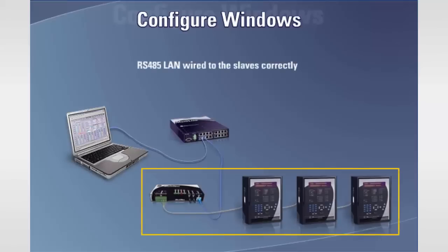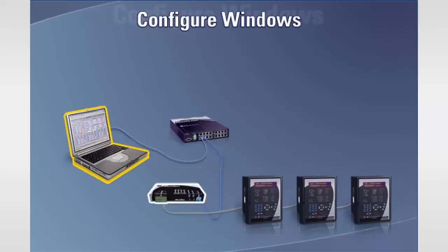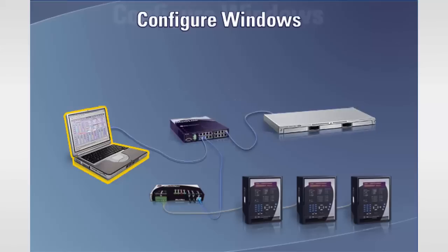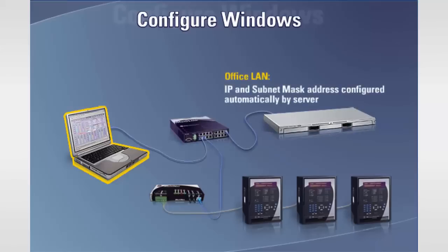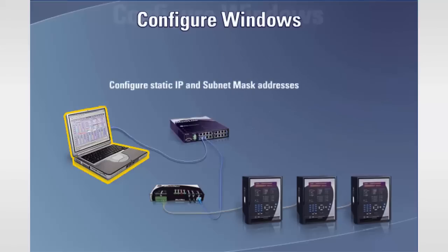We will assume that the RS-485 LAN has been wired to the slaves correctly and each relay has been assigned a unique Modbus slave address in addition to matching baud rates and parity. We will focus on the configuration of the computer and the Multinet. The first step is to configure the computer's IP and subnet mask addresses. Without these addresses, a device cannot communicate over an Ethernet LAN. Within an office LAN, this configuration is normally performed automatically by other computers on the network called servers which are running special software. Relying on a server to perform this function within a protective relaying LAN isn't desirable as a failure of the server could result in failure of the entire Ethernet LAN. A provision is made within the computer to configure permanent, or static, IP and subnet mask addresses such that a server isn't required.